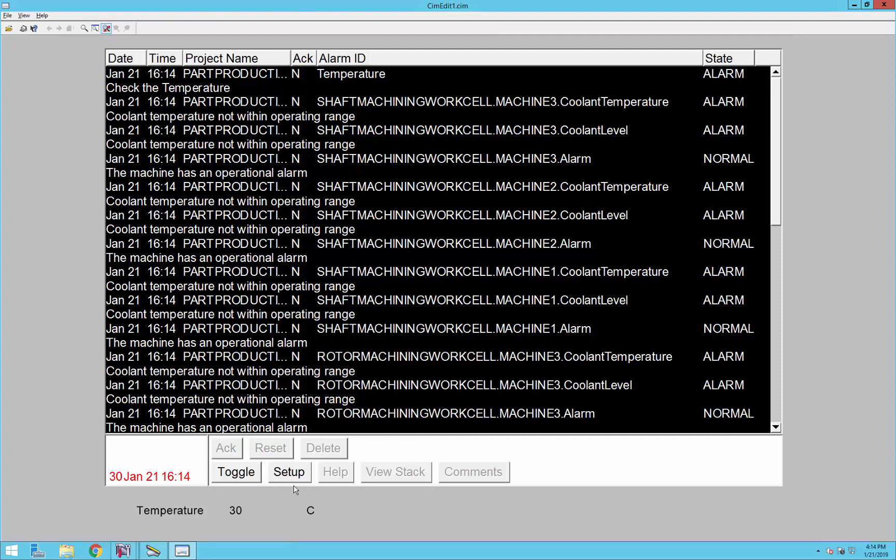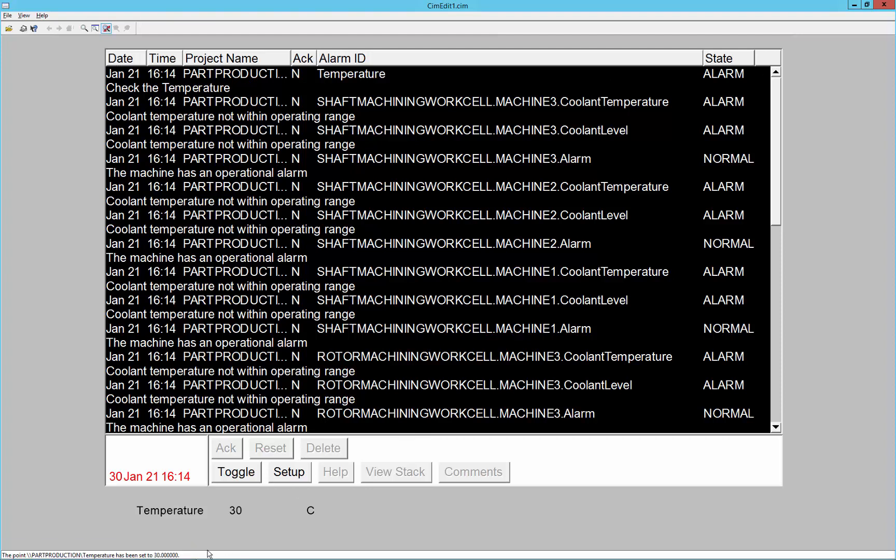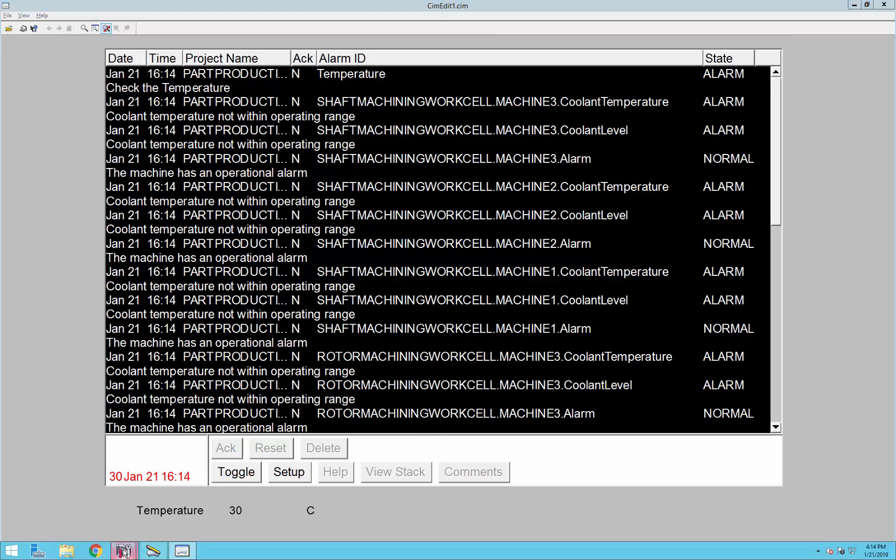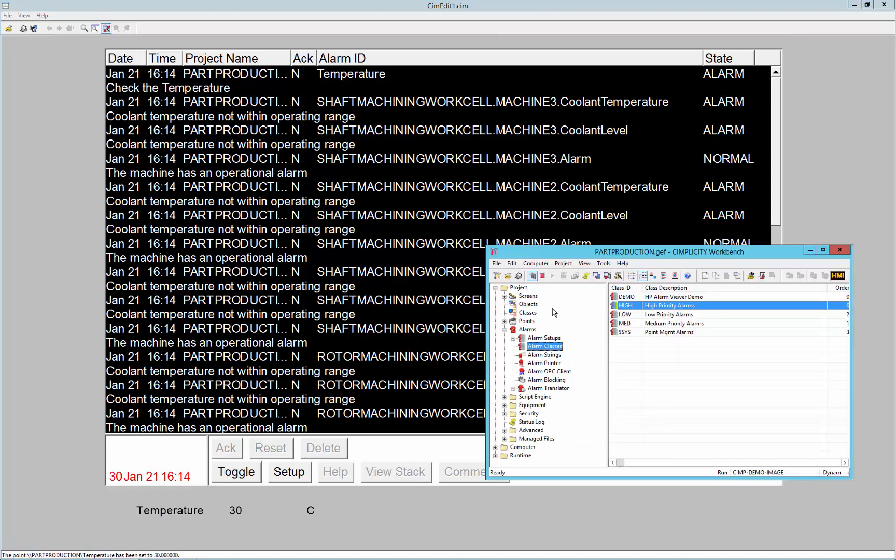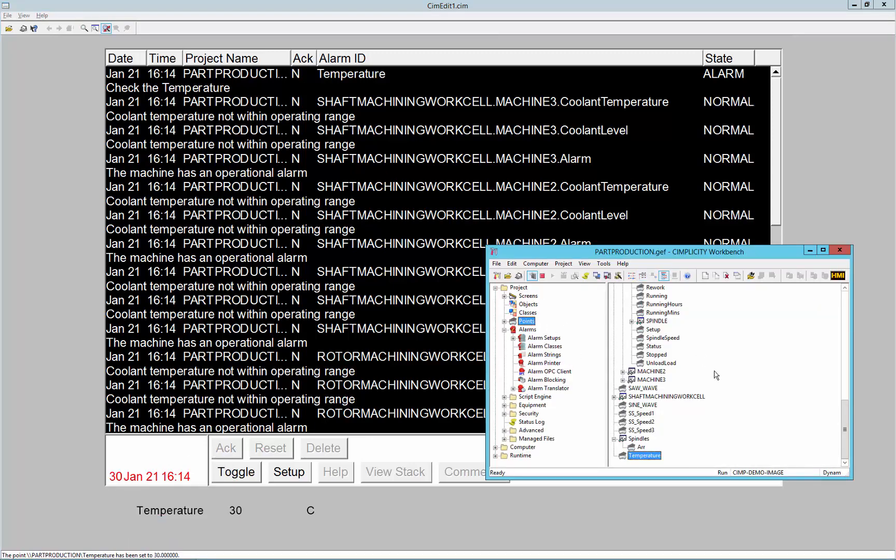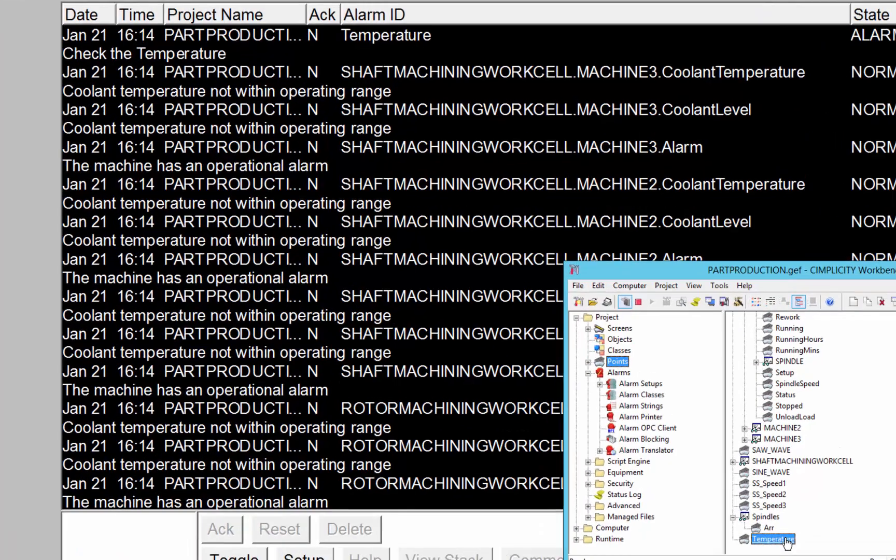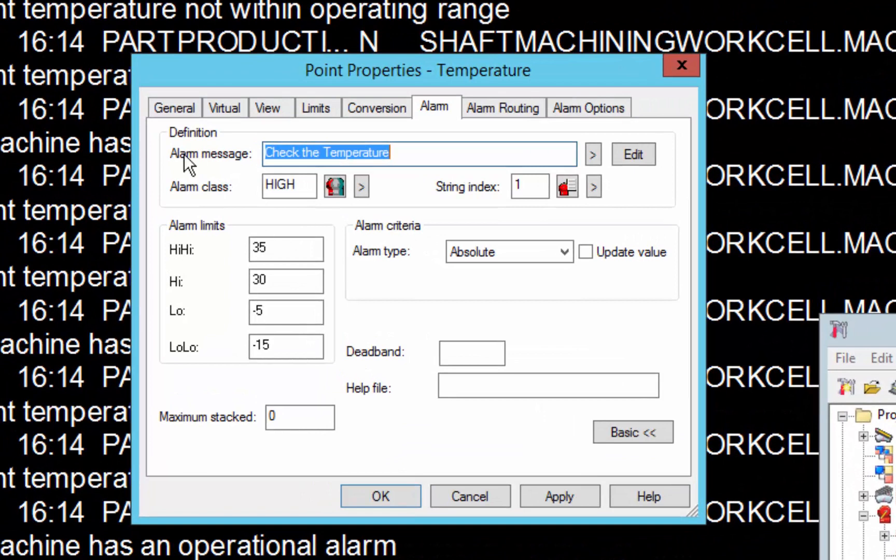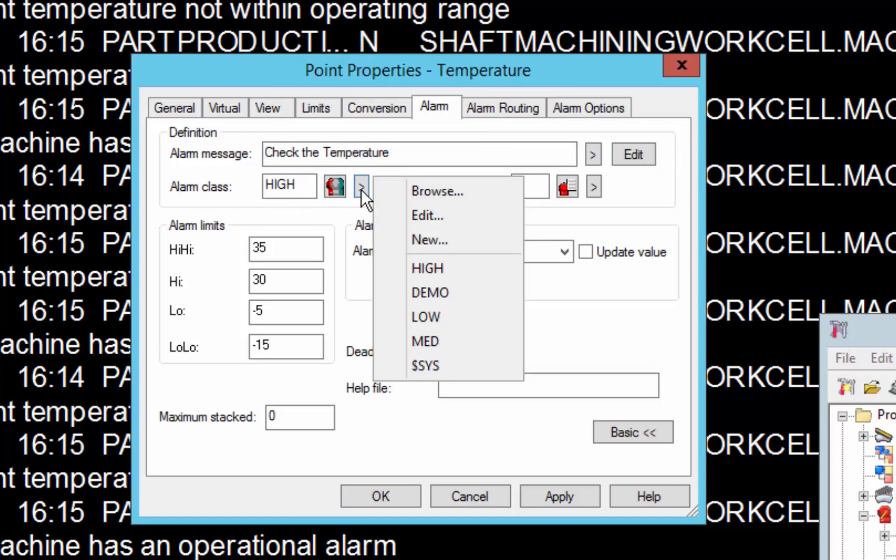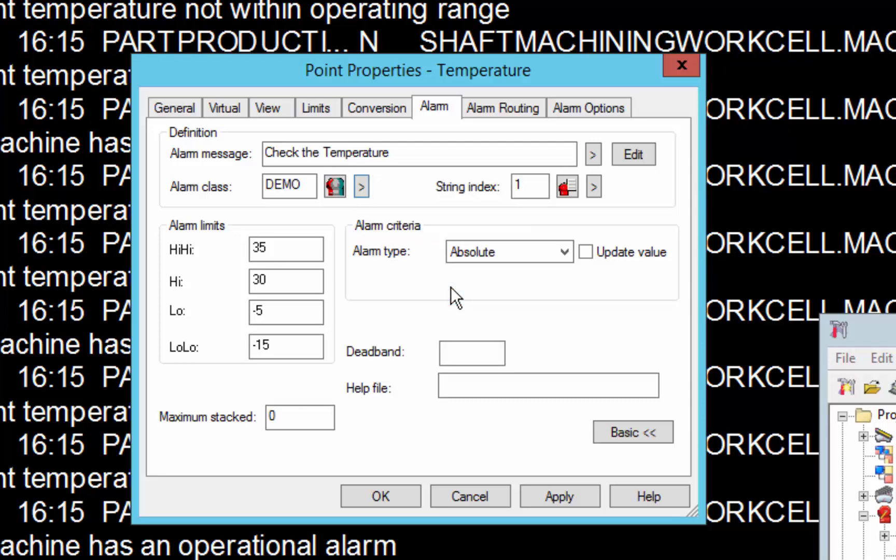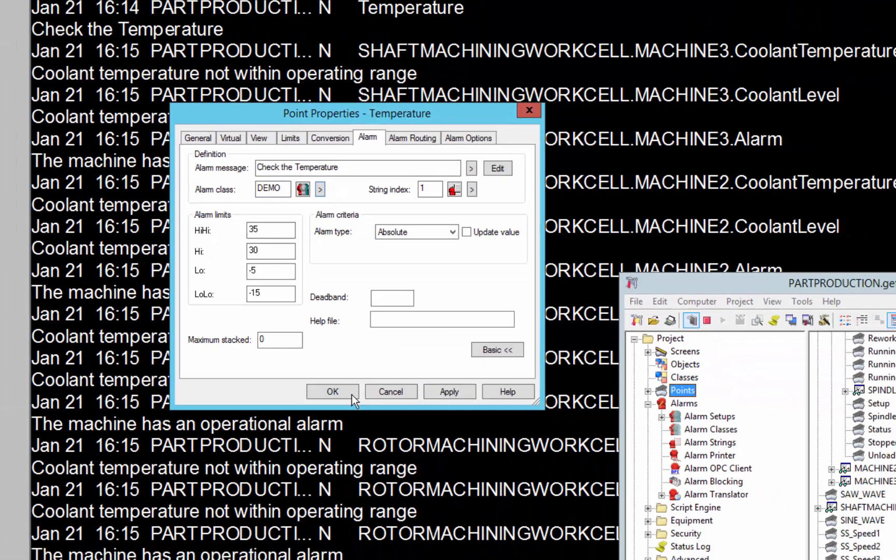So if I want to change that, I can go into my point in my points database, go to the temperature, and you can see under the alarm tab, you can set the alarm class for any given point that has an alarm in it. So I'm going to change our alarm class to alarm demo, or to the demo class.